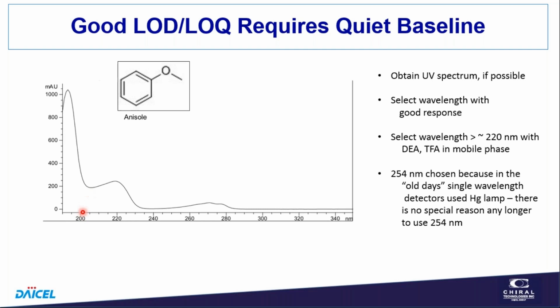In this region around 200, the diode array detectors, for example, can go down to the 190, 200 region, but most of the solvents we have absorb in this region. So their UV cutoffs are somewhere around there, depending on what solvent it is. Methanol, I think, is around 205. So you may get some response background due to the solvent. Just attenuate your response. It shouldn't interfere.